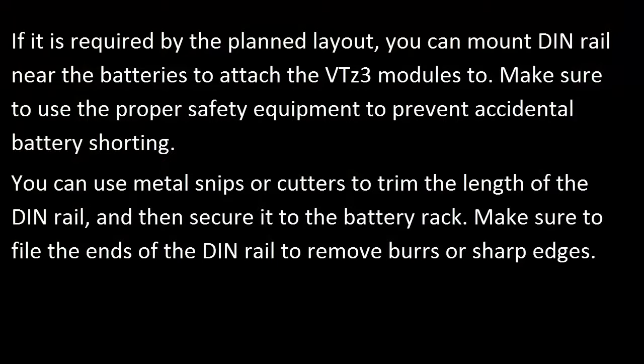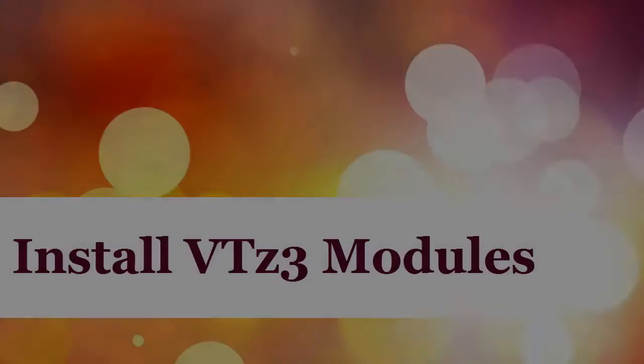If it is required by the planned layout, you can mount DIN rail near the batteries to attach the VTZ3 modules to. Make sure to use the proper safety equipment to prevent accidental battery shorting. You can use metal snips or cutters to trim the length of the DIN rail and then secure it to the battery rack. Make sure to file the ends of the DIN rail to remove burrs or sharp edges.